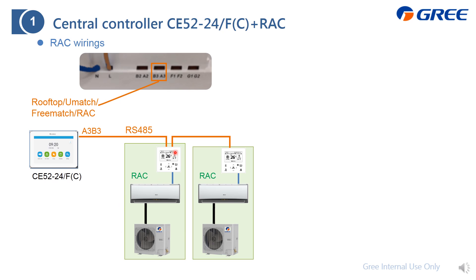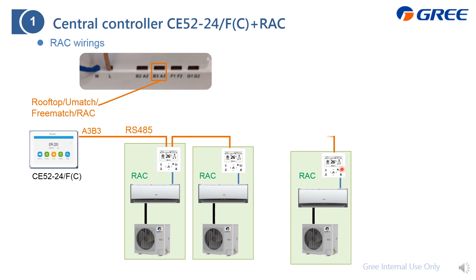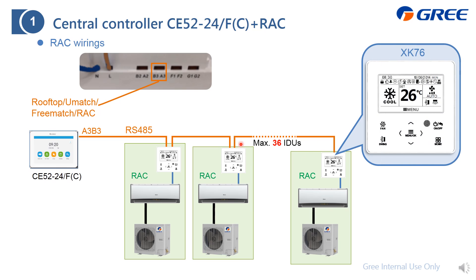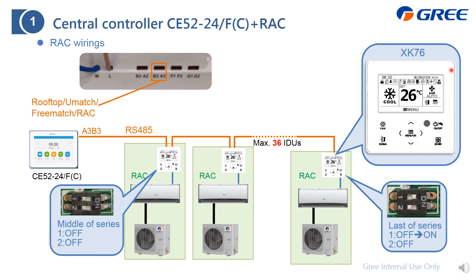You can find that we actually control the wire controller, not the indoor unit directly. But through the wire controller, we can fully control this residential air conditioner. Just connect to A3B3 here. It can connect to the MAX36 residential air conditioner. The wire controller is XK76, and it is an RS485 connection. We recommend adding a 120-ohm resistor. Here is the part code just for your reference.